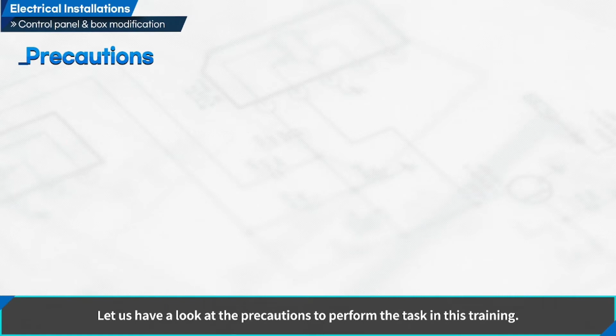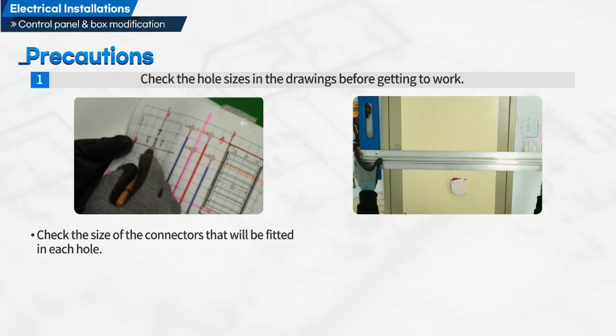Let us have a look at the precautions to perform the task in this training. First, check the hole sizes in the drawings before getting to work. Check the size of the connectors that will be fitted in each hole. Check the gap between the apparatus accurately before drawing. Second, when punching out holes, they should be done at the exact points where holes should be made. Place the center punch at the exact point where holes should be made and punch out the hole while holding the center punch vertically. If the center punch is slanted during the work, errors in hole size may occur when working with a hole saw.